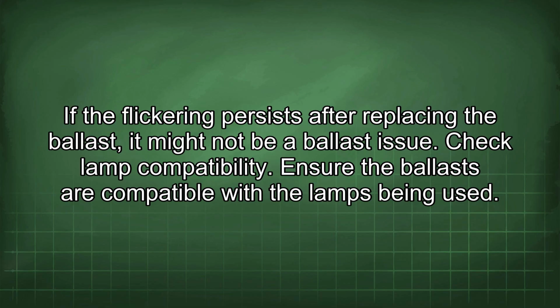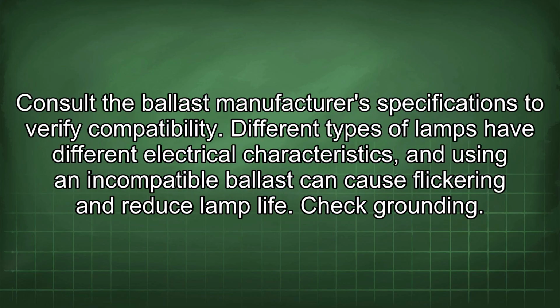Check lamp compatibility. Ensure the ballasts are compatible with the lamps being used. Consult the ballast manufacturer's specifications to verify compatibility. Different types of lamps have different electrical characteristics, and using an incompatible ballast can cause flickering and reduce lamp life.